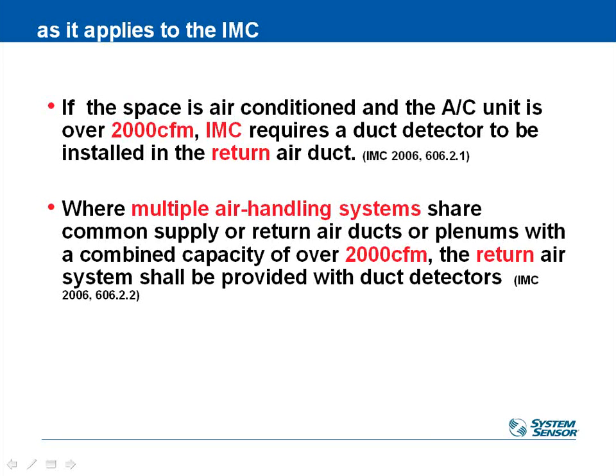Additionally, on the IMC, if you have multiple air handlers sharing a common duct, and that common CFM is more than 2,000 CFM, then you also have to do it. So in this example, maybe you've got 2 4-ton furnaces twinned together. Neither one of them is 2,000 CFM on its own, but together 2 4-ton furnaces would be 2,000 CFM. So you would have to have the detector in the return duct.